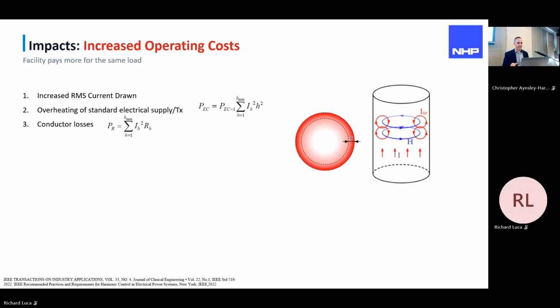Conductor losses. Everyone knows the I²R losses in a conductor. The square of the current times the resistance will give you the power loss. But there's also skin effect. Introducing these harmonic distortions in the system, additional frequencies, has an effect. So we've got a cable here, the current that's flowing through the cable in red. In blue, we've got a magnetic field around that cable that's pulsing, and then we're introducing eddy currents around those magnetic fields. So what happens is the eddy currents push the current through that conductor away from the center of the conductor to the outer edge. So this is called the skin effect.